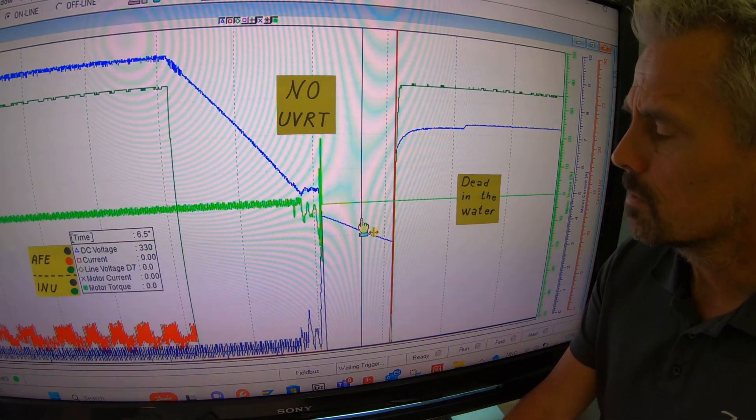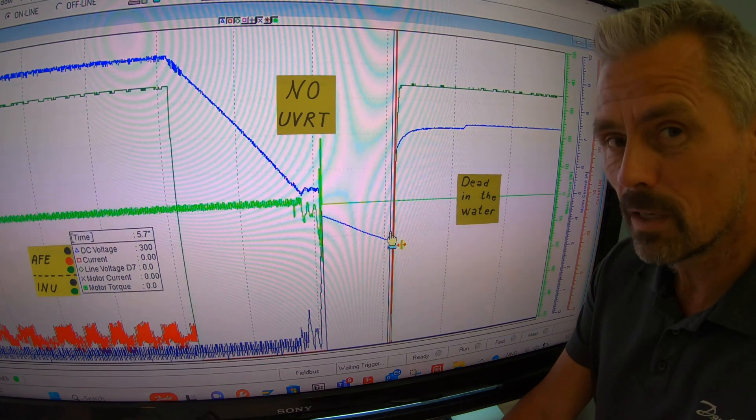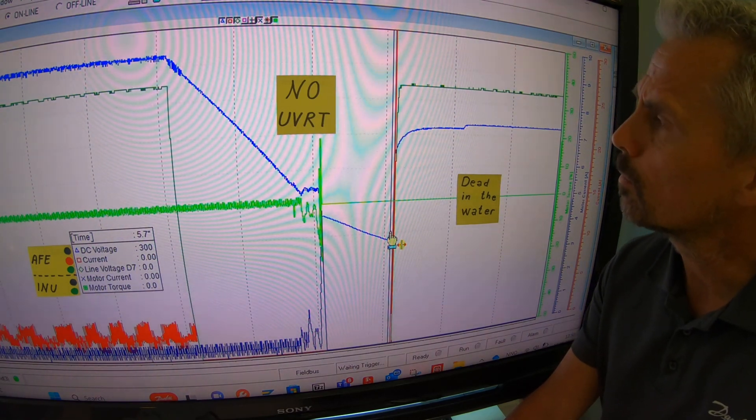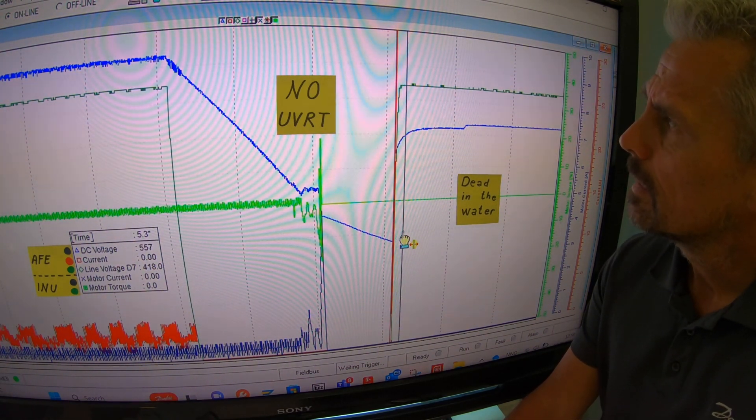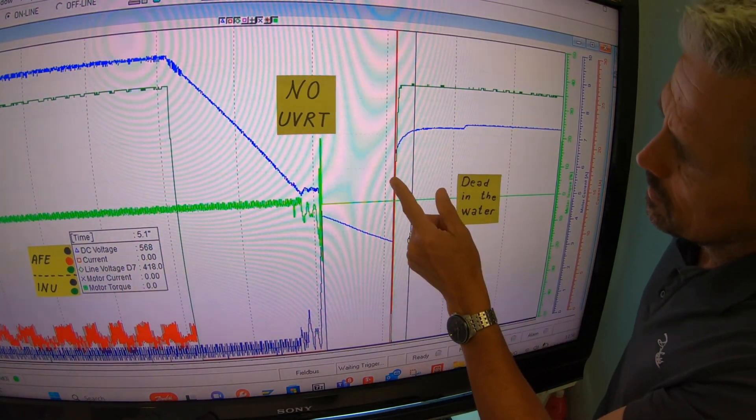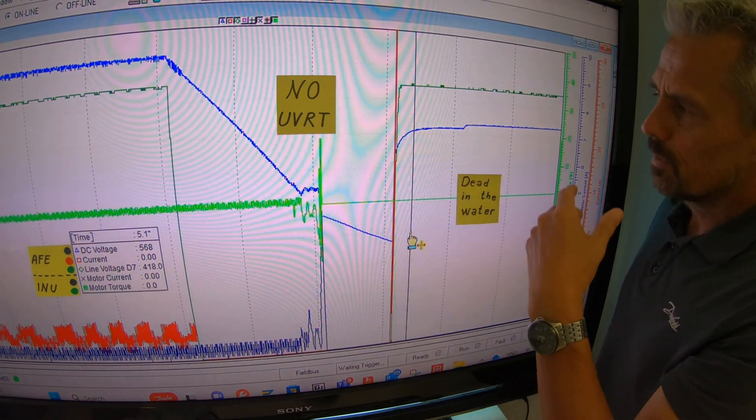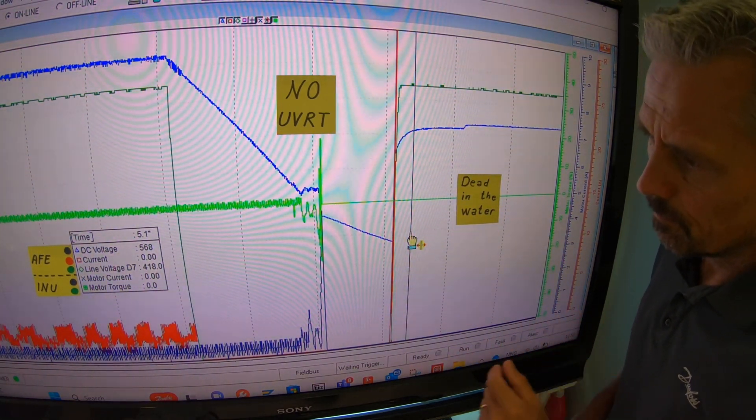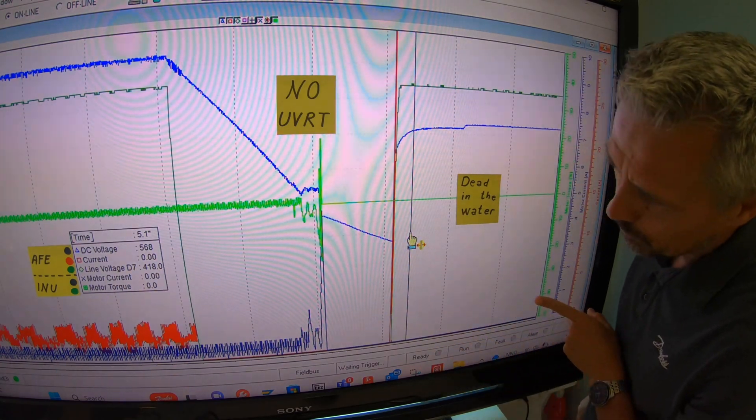So the DC voltage keeps on plummeting down to 300 volts and you probably have an undervoltage trip on most of the drives. Here, the AC voltage is restored. The DC voltage comes back from the pre-charge circuits and also the freewheeling diodes. But there is no start-up of the active frontend. The active frontend doesn't start. The consumer doesn't start.